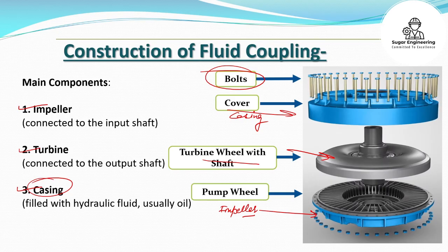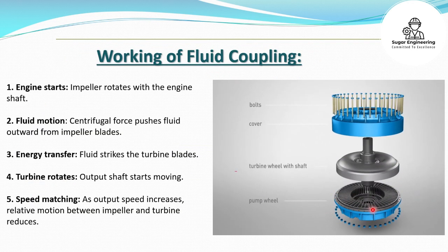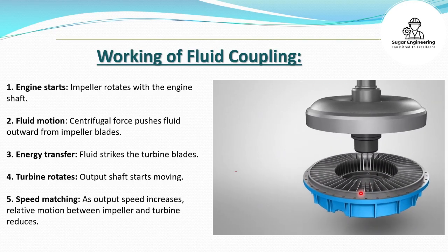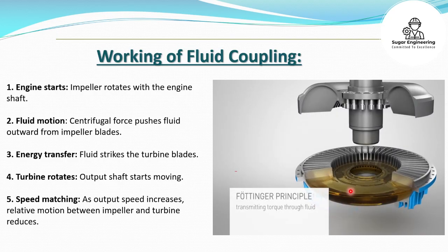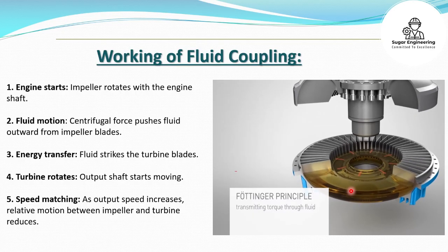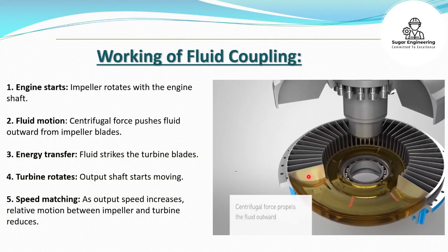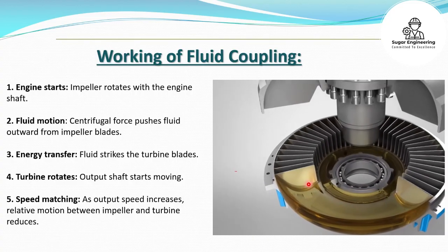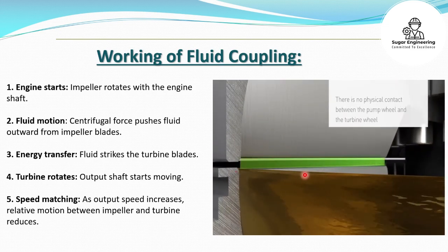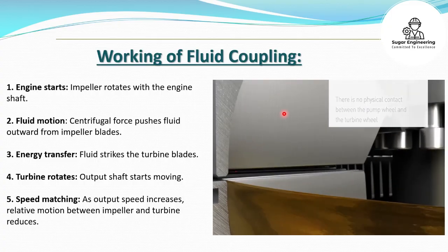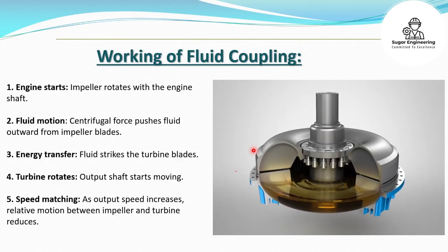Now we will discuss the working of the fluid coupling. This is the pump wheel and it is connected to a motor or any prime mover. A fluid known as oil is filled in the casing of the fluid coupling, and the torque transmission is done through the fluid. As the pump wheel rotates, centrifugal force is generated that pushes the fluid outwards from the impeller blades. There is no contact between the pump wheel and the turbine wheel, so there will be wear-free torque transmission from the input shaft to the output shaft using a fluid coupling.